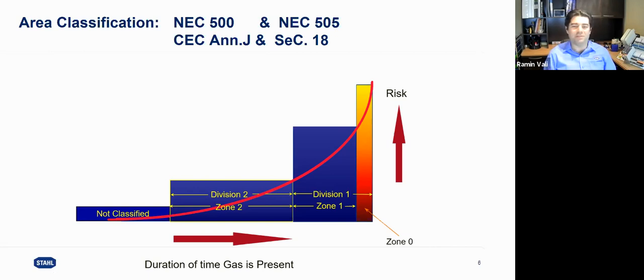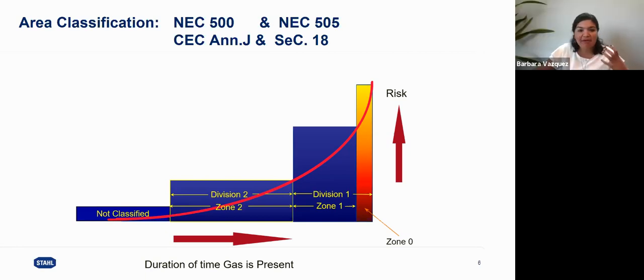For example, an HMI computer for Class I Div. 1 most of the time has to be purged, because some of the protection methods recognized in Div. 1 force us to use purge panels for Class I Div. 1. However, when we switch to the zone concept, most of the time this area is reclassified as Zone 1 and not Zone 0. So we have more options to choose a proper protection method. That means we have more options to use HMI panels without a purge requirement, and of course that means saving a lot on purge procurement and operation over time. We will talk a little more about those protection methods and which ones are recognized where. That was very interesting to know.